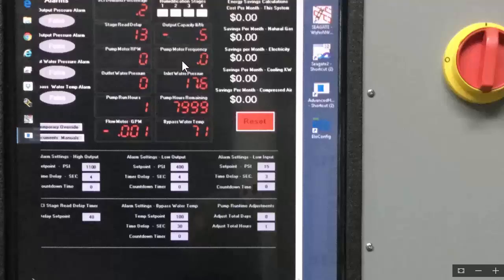Since it's not running, pump frequency is 0, and this is input water pressure. So that is the pressure at the incoming water transducer. It says it's 17.6 pounds. That's past the solenoid, so it's dropped off a little bit. It's not actual real pressure coming into it. And here is bypass water temperature, which we'll talk about in the bypass circuit. And here are bypass water temperature set points, and pump run hour adjustments that actually adjust these run hours if you put a new pump in there or you do some maintenance on the pump. And then here's an override alarm, which we'll talk about during operation of the unit.